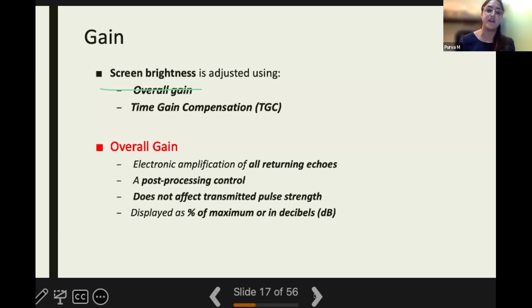The gain will amplify only the electronic signals produced by the returning echo, while the power generally does so of the transmitted wave that is going into the tissue, thereby increasing the thermal index and the mechanical index, while this is a post-processing control. So this only increases the amplification of the returning echoes. We can either increase the overall gain, or we can increase gain only in a part of the image.